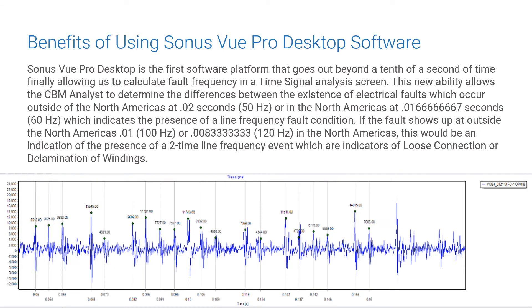Sonus Vue Pro Desktop is the first software platform that goes out beyond a tenth of a second of time, finally allowing us to calculate fault frequency in a time signal analysis screen. This allows the CBM analyst to determine the difference between electrical faults occurring outside of North America at 0.02 seconds (50 Hz), or in North America at 0.016666666667 seconds (60 Hz), which indicates the presence of a line frequency fault condition.